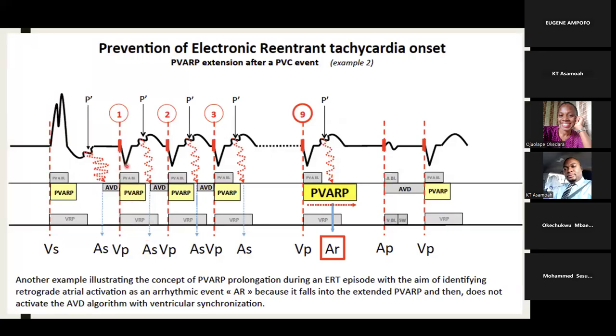So you have the, what's it called, ventricular spike. There's a retrograde P wave, and the atrial lead sensed it. So it started the AV interval. Then you had another retrograde P wave, and then the atrial lead sensed it. So you can see here A sense.